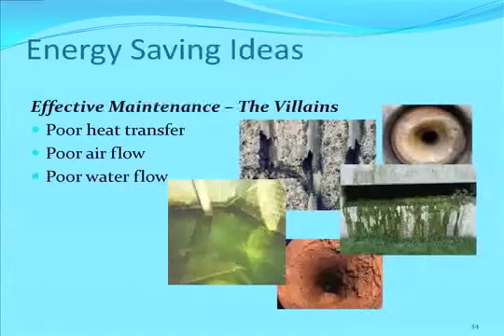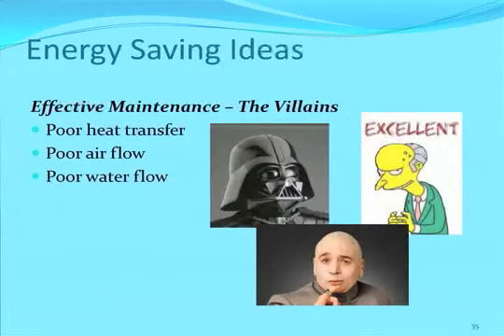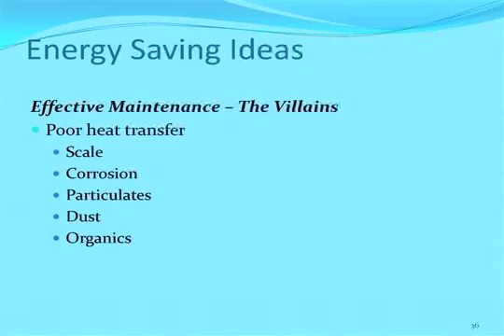The villains: poor heat transfer, poor airflow, poor water flow. Here's some pictures. Here are some other pictures. Under poor heat transfer, scale, corrosion, particulates, dust, and organic material interfere with the heat transfer capability, whether it be in the cooling tower air side or the water side in the pipes.